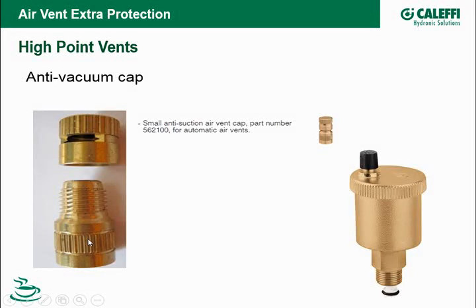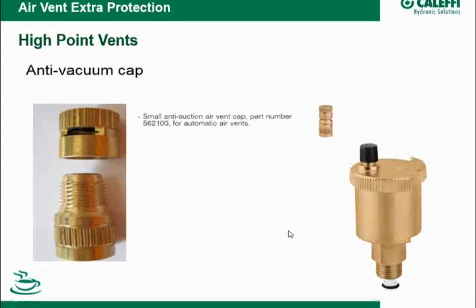Now, it's a Band-Aid of sorts. If you are getting air into a system, you should really find out what's causing that and fix that. You know, this treats the symptom. It doesn't really treat the problem, but it is a handy little part to have a couple in the glove box of your truck. So if you've got a system where you don't have time to go back and change the piping or correct the problem, you can just put this on, at least solve the problem until you can get back at a later date and correct the cause of the problem. We do sell that as just a little standalone piece. It does fit a lot of different brands. This is a fairly common thread that you'll see from brand to brand on the top of this, so check that out if that's something you think might help you.